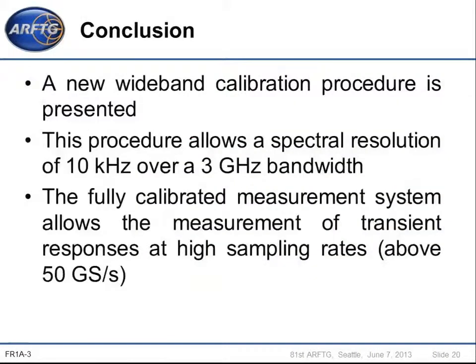Finally, to conclude, we have proposed a wideband high-resolution calibration procedure. Using this procedure, a 10 kHz resolution is reachable over a 3 GHz bandwidth. The fully calibrated measurement system using this procedure allows accurate measurement of transient responses at high sampling rates. Thank you.